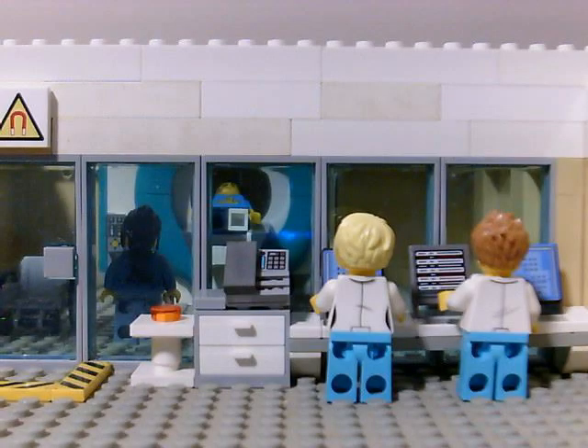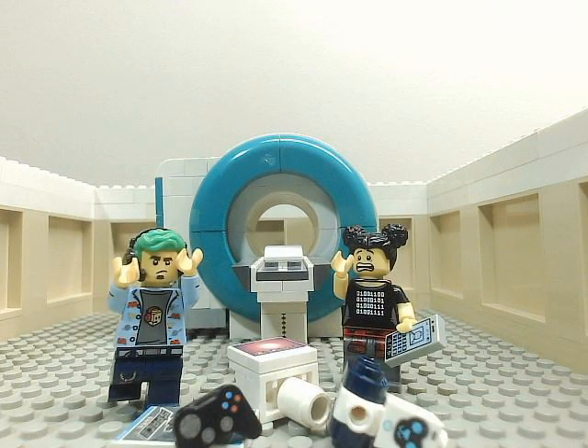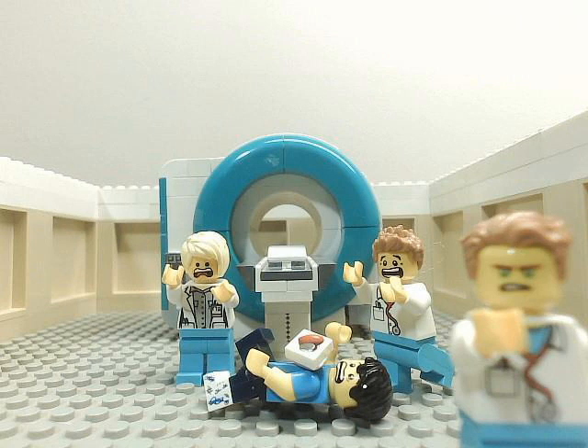Such unsafe things should be securely stored in the designated areas outside of the magnet room or in the control room, or be properly secured by a member of the MRI team. Electronic devices need to stay out of the magnet room. Their batteries are almost always magnetic and the magnetic field of the MRI can break them. This includes electronics inside of you — people with pacemakers, neurostimulators, and medicine pumps can be seriously injured or killed from malfunctions of the devices when near MRI systems.